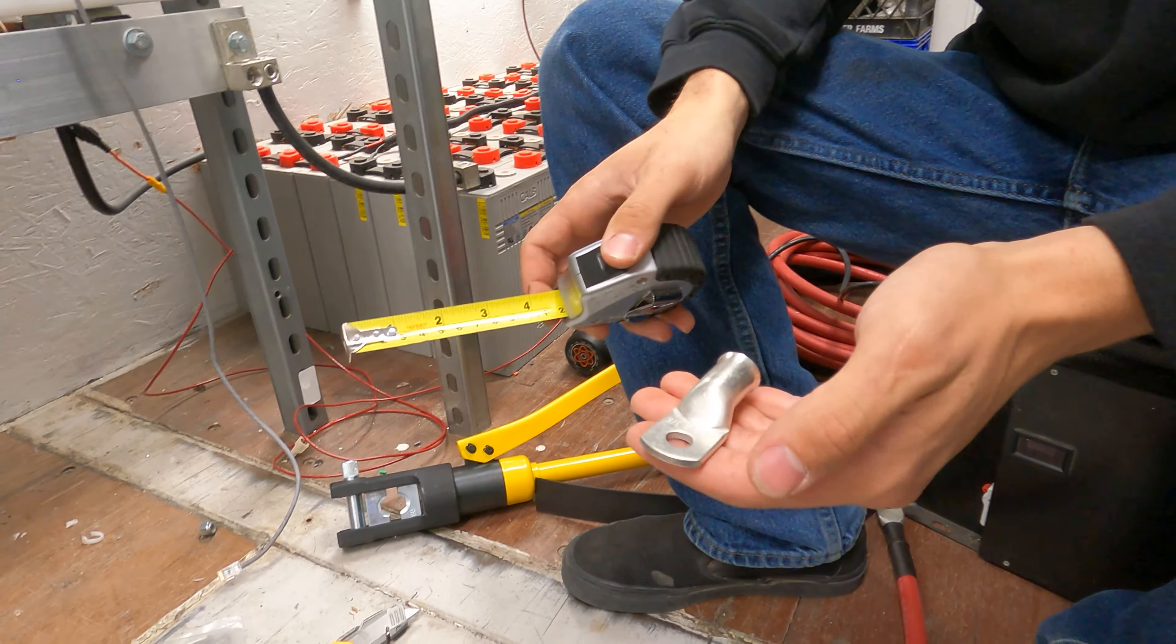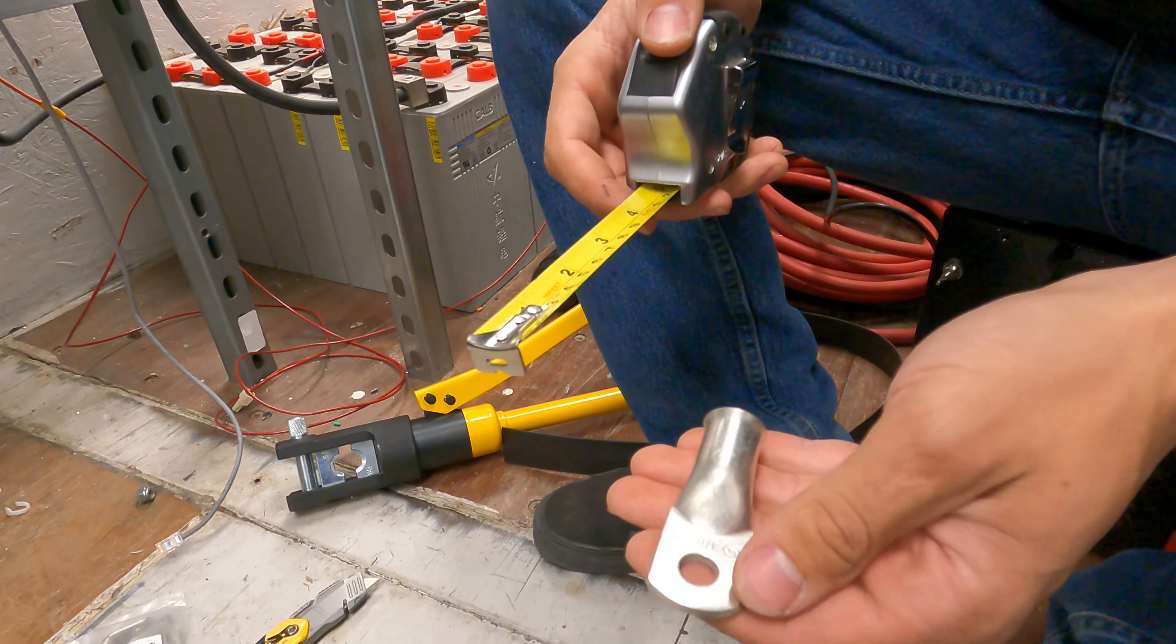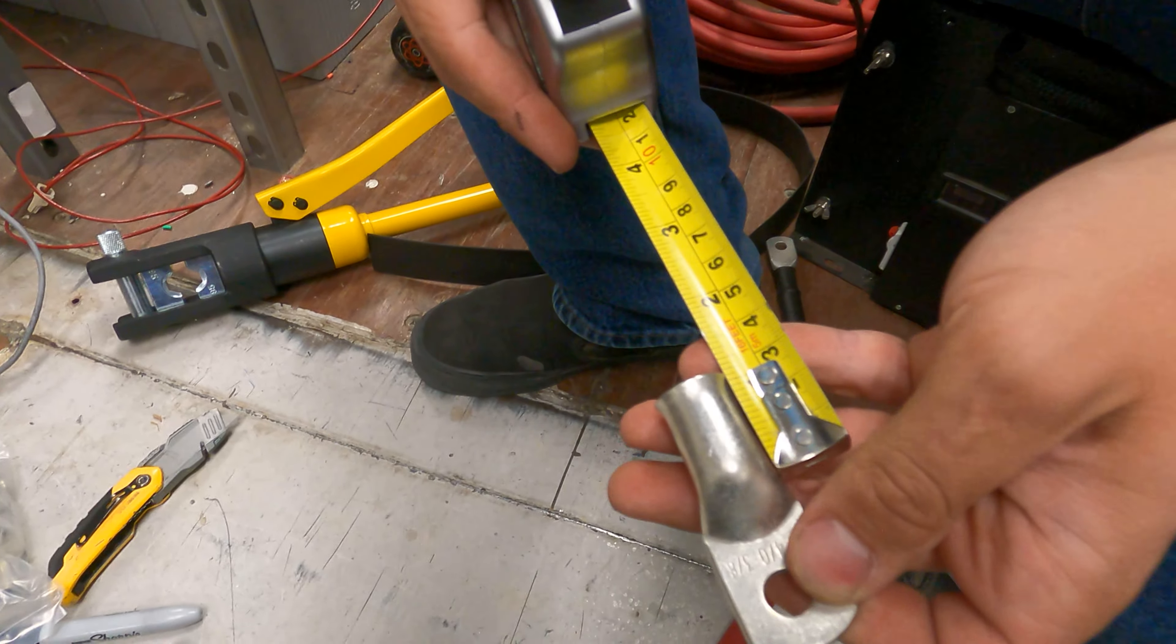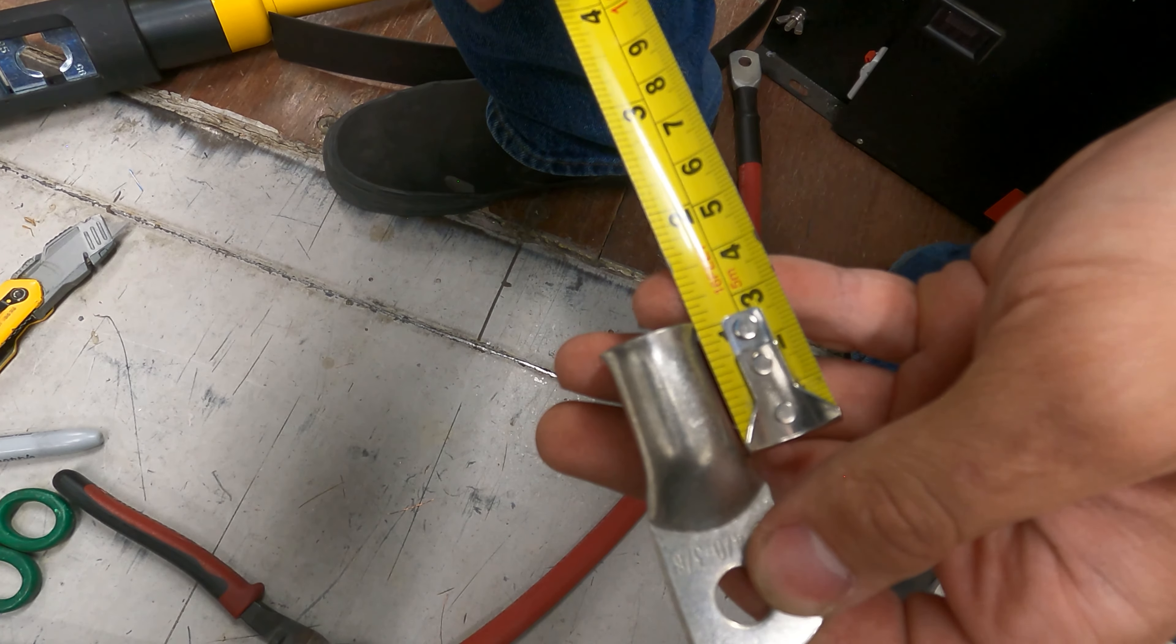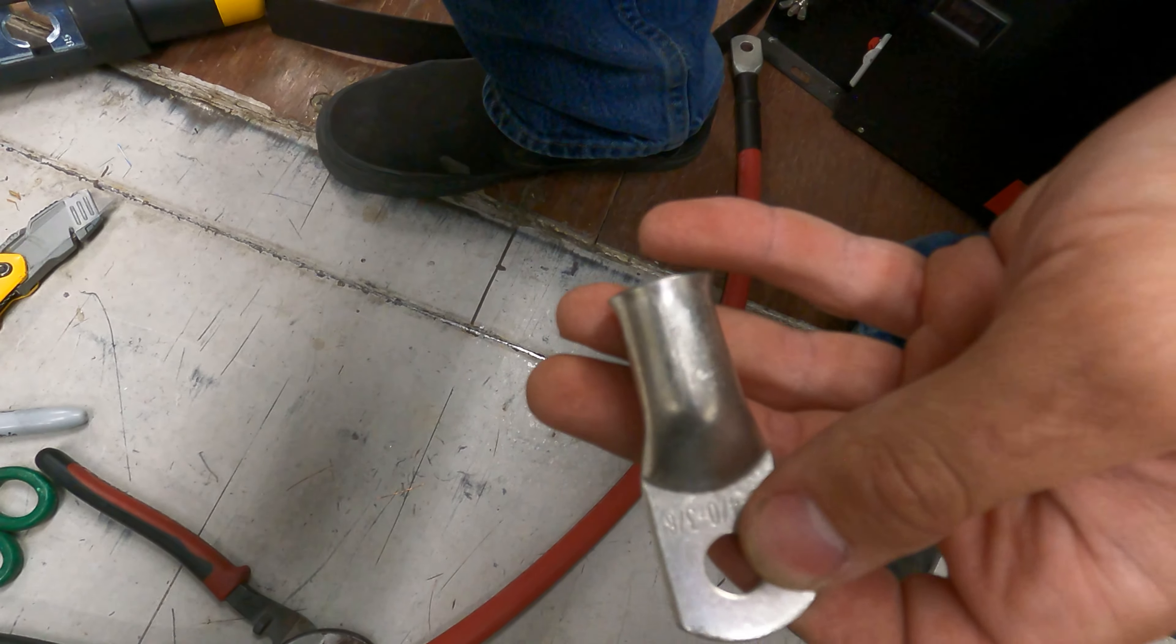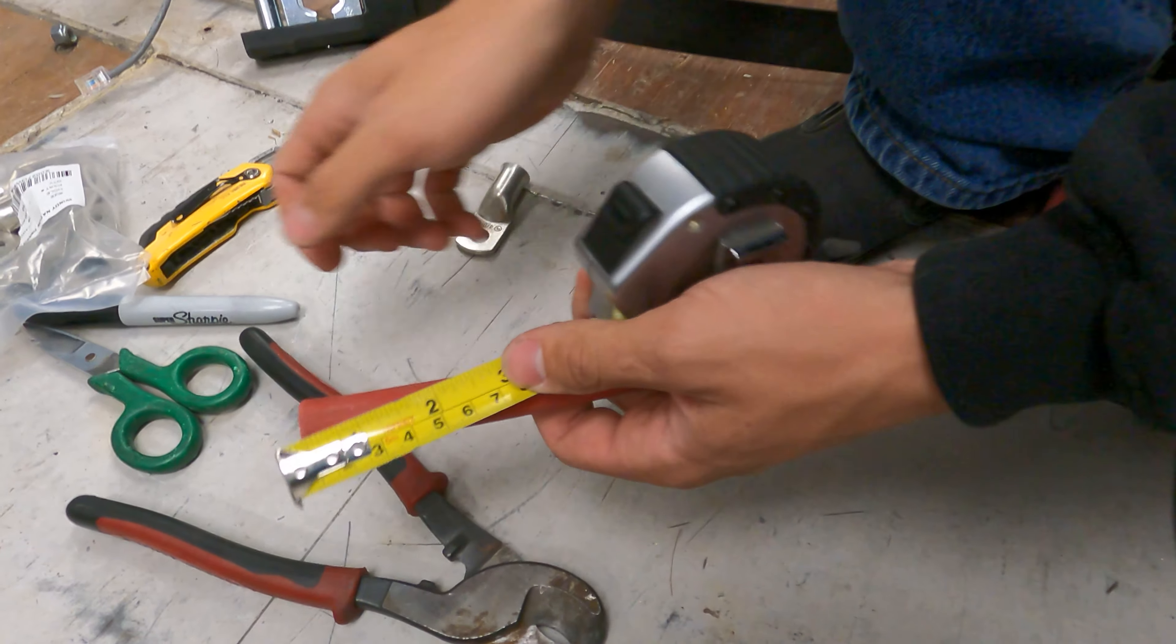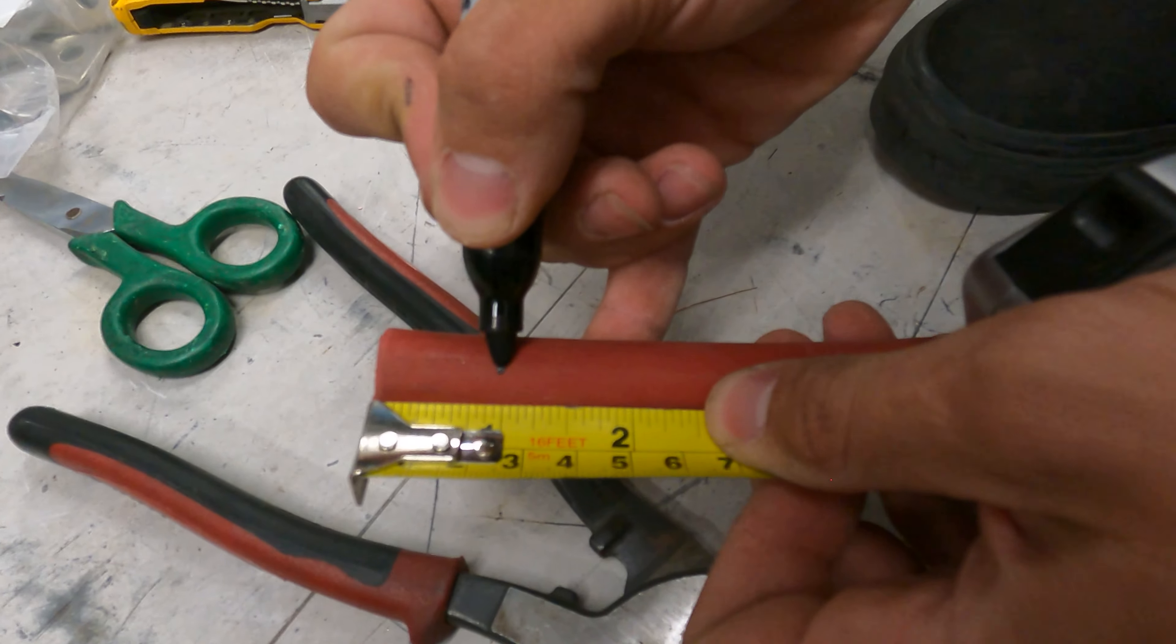Okay, so the first thing we're going to want to do is take our tape measure and measure how far we need to strip back our insulation. In this case, the lug starts tapering down after about one inch of depth, so we're going to strip back one inch of insulation on this wire. I'm going to take my tape measure and my sharpie, and one inch back, I'm going to make a mark.